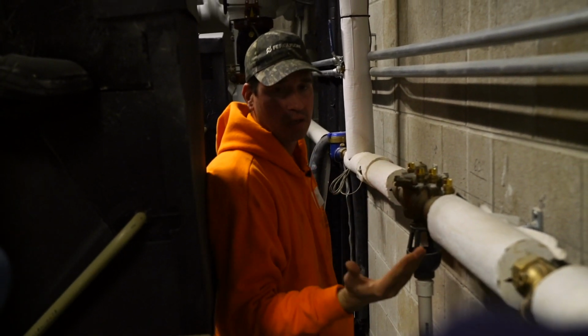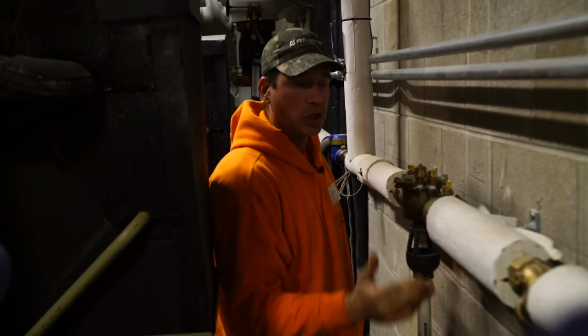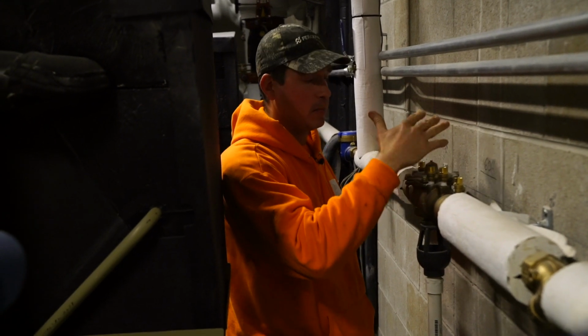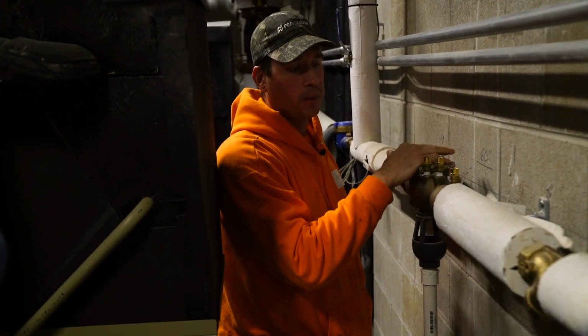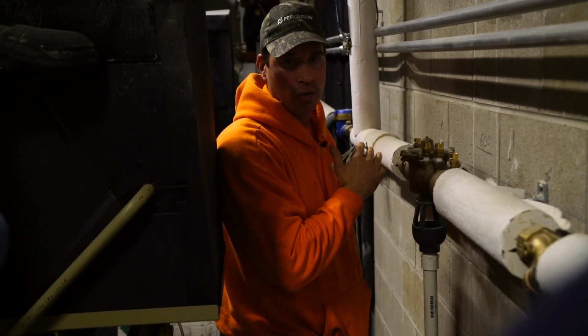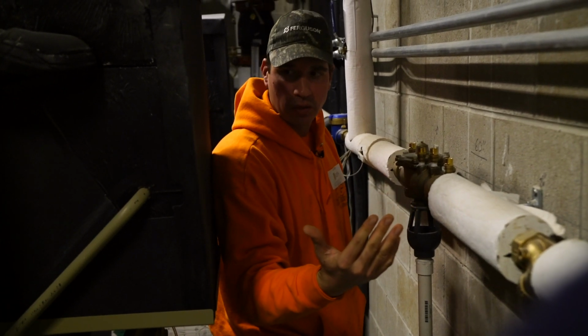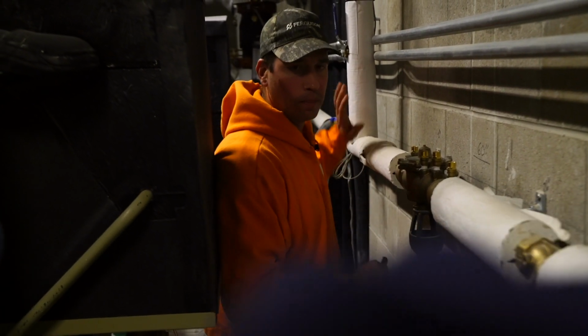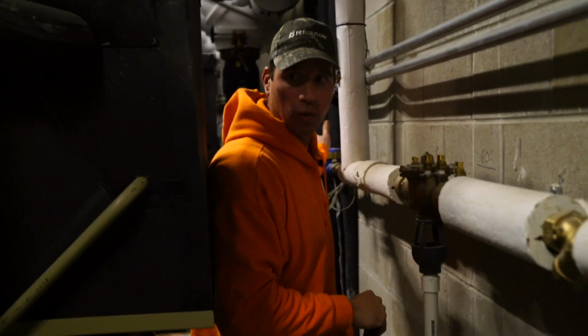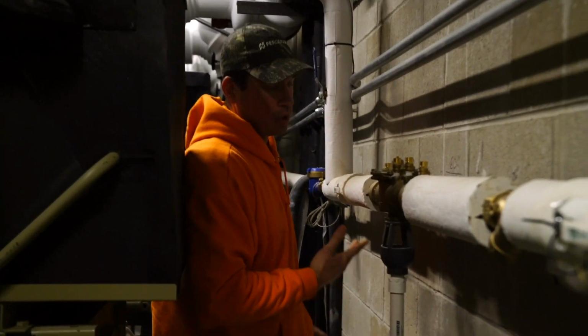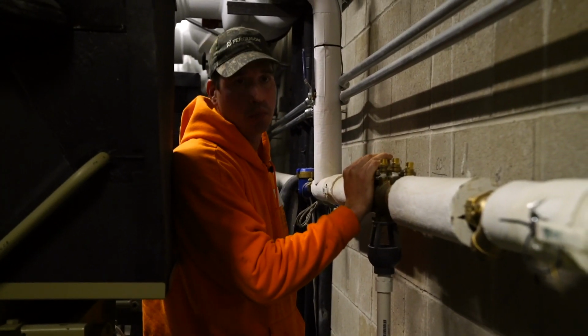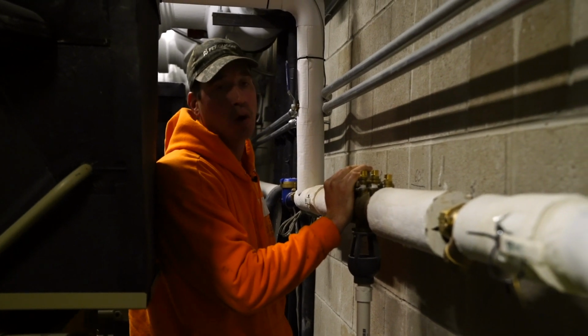I'm certified. I tested them all as we installed them. They should be done yearly just because of that, and make sure they're working properly. Like I said, you don't ever want any cross-contamination for some reason back into the building with the non-potable water that it's feeding, whatever equipment. So that's up to the commission what they want to do, but these should be tested annually. In New Jersey, that's law.